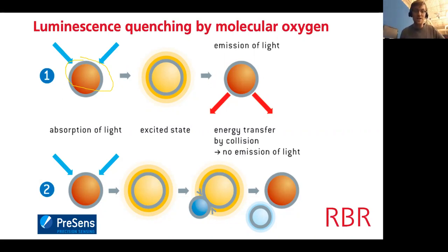at which point the luminophore then emits light back to the photodetector. Now, when oxygen is present in the environment, it collides with the luminophore, and the energy from the luminophore in its excited state transfers to the oxygen molecule, and the luminophore returns to its original non-light emitting state. The sensor then measures the rate at which this illumination is quenched, and that is proportional to the amount of oxygen in the environment. Next slide, Eric.